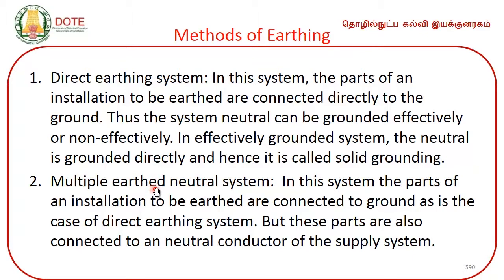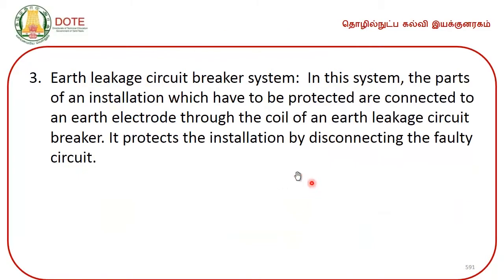Number 2, multiple earthed neutral system. In this system, the parts of an installation to be earthed are connected to ground, as is the case of the direct earthing system, but these parts are also connected to a neutral conductor of the supply system. Number 3, earth leakage circuit breaker system. In this system, the parts of an installation which have to be protected are connected to an earth electrode through the coil of an earth leakage circuit breaker. It protects the installation by disconnecting the faulty circuit.